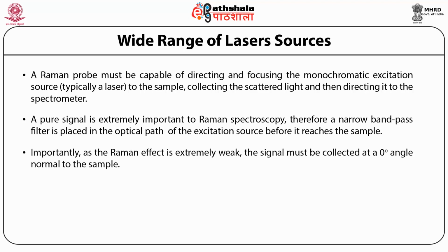Importantly, as the Raman effect is extremely weak, the signal must be collected at a 0-degree angle normal to the sample. This causes interference from Rayleigh scattering, and therefore it is necessary to filter the collected signal via a long pass filter before it is directed to the spectrometer.